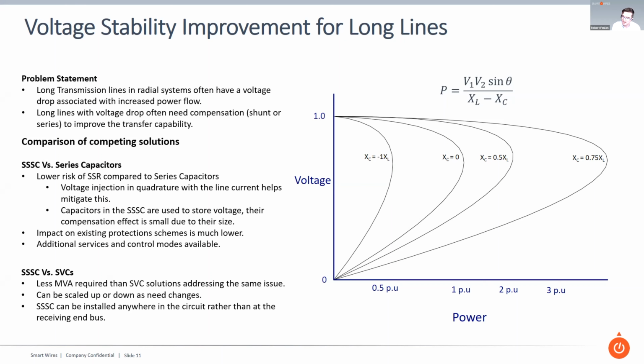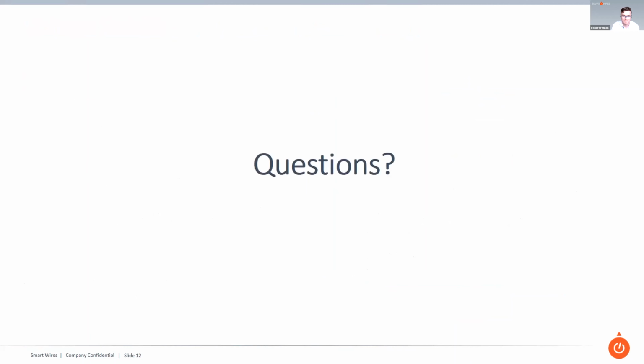And then the SSSC was also able to be installed anywhere along that circuit. So at the sending end, at the receiving end, or in the middle of that circuit, it doesn't really matter, because the compensation level is going to cancel out some inductance somewhere. It doesn't matter where you put it, whereas the SVC has to be installed at the receiving end bus to have the same net effect. So those are just two applications that I wanted to explain, to show the benefits of the SSSC, and that's the end of the presentation. So if there are any questions from the group.